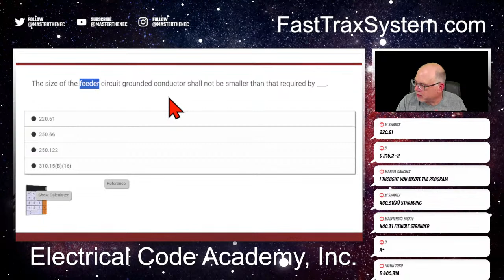That type of thing. Swartzy says 220.61. Now, 220.61 talks about how you can reduce the size of the neutral, and when you can and when you can't for the load calculation. But there's rules that determine a minimum size, even though the calculation is going to result in a bigger one. Usually there are minimum sizes that we have to meet. Okay, so think about that one again, Swartzy, and we'll go over to the code. All right, so the first thing that triggers to me again is feeder, right? So I'm going to go to the NEC, and I'm going to go to 215, which you should know is actual feeders.